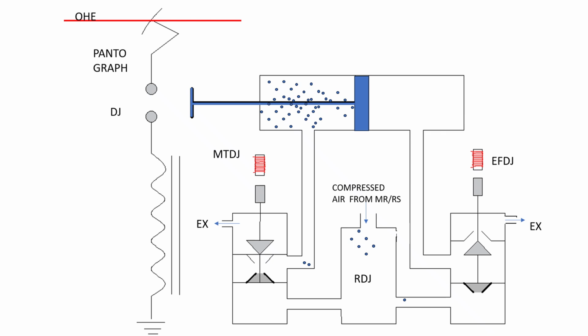In the DJ closing circuit, we have seen first Mtdj will energize, then Efdj will energize. Mtdj will release the air in the left side of the chamber, and when Efdj will energize, it will send the air pressure to the right hand side chamber, and the DJ will close. So this is the system. See how it is happening. But in the next slide, I'll show you the animation. Here, I am showing you just the basics.